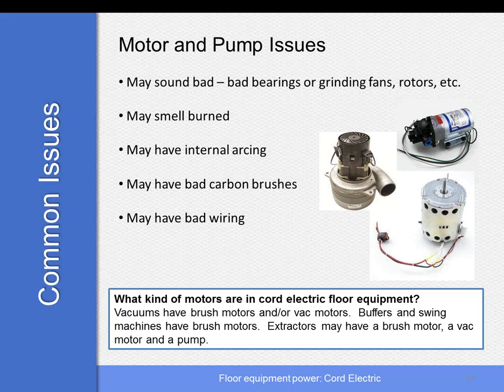There's fans, cooling fans inside motors that can rub against housings. The rotors, the windings itself, those can come loose or melt and start to make contact. You may have a bad smell. That's usually from the arcing inside.